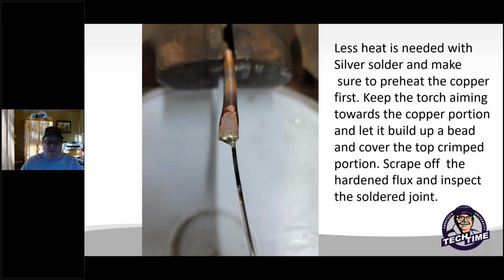Now, remember, less heat is needed with silver solder. This is more similar to your regular soft solder plumbing joints, but again, it's the same scenario. Keep your torch aimed away from the small tube, because you want the solder to be sucked into your pinch section, and then back away your torch. Again, back away your torch tip and reduce the heat going through there, and you can lay a nice bead like I'm showing on that one there.